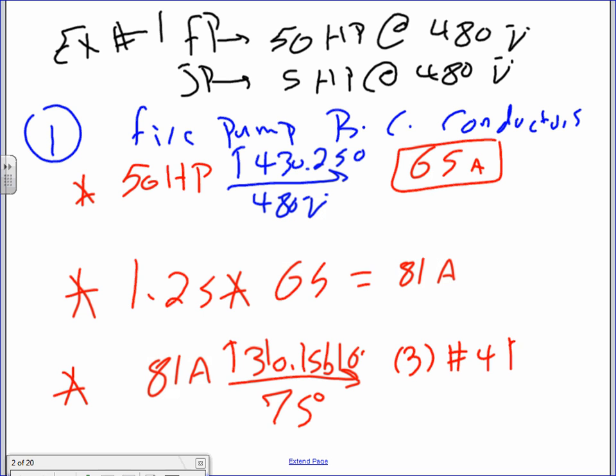number 4 RHW, an insulation I use with the fire pump. RHW, not THHN, an RHW. More robust for the fire pump. Any comments? Any questions? Does that make sense, everybody? See how that is easy? On the test, there is no reason not to ace it. You have that sheet in front of you?